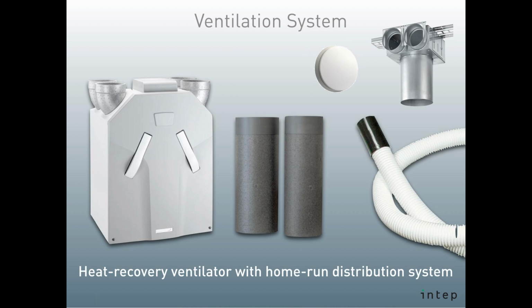At the heart of it, on the left, we have the heat recovery ventilator. In this case it's a Zehnder Paul Novus 300 machine. The big pipes going to and from the outside are called ISO duct, or Comfo pipe as Zehnder calls it—it's insulation and duct in one, made from EPS foam, so it just plugs together. It's a basic, bulletproof system.